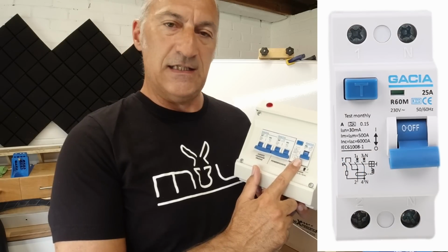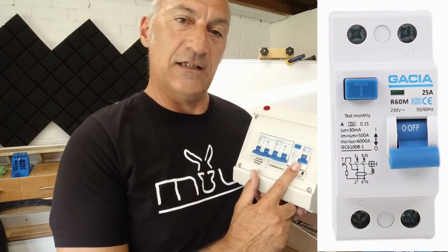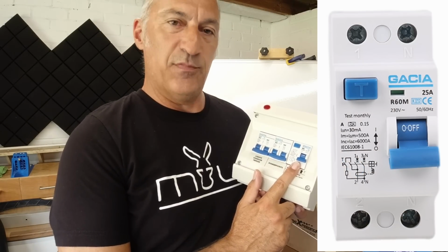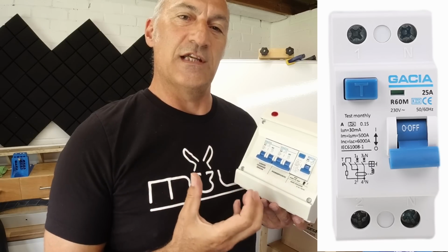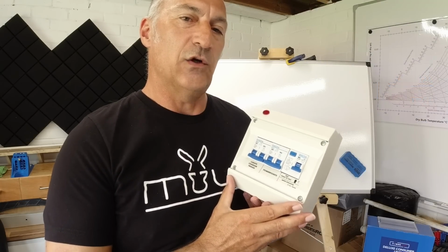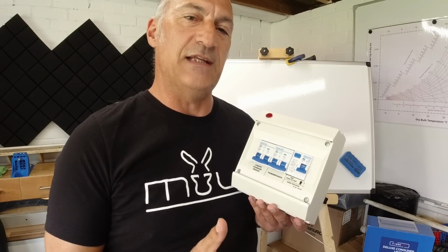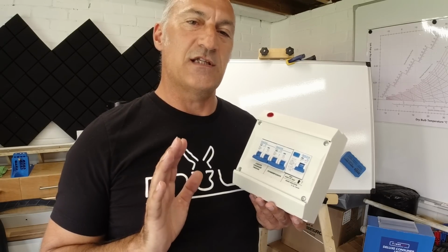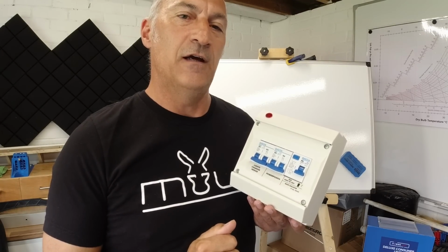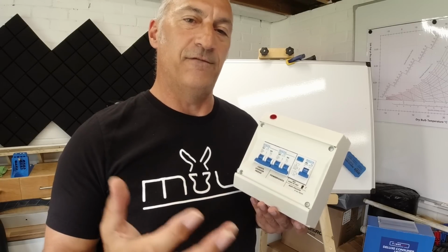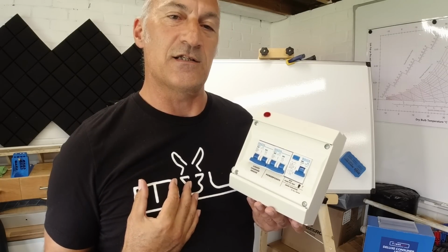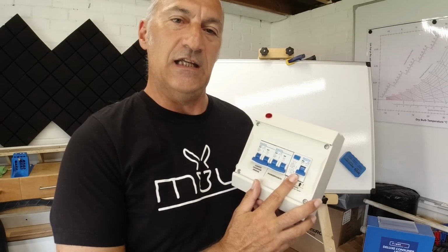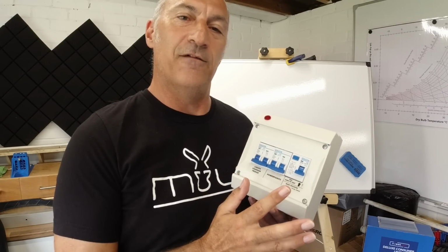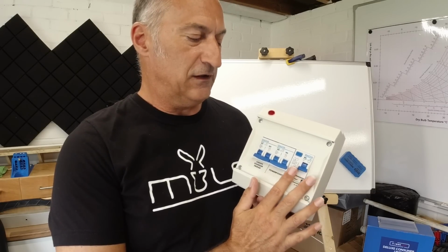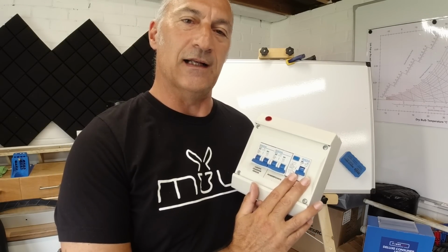There's an RCD or residual current device, and this is here to protect us from receiving a fatal shock. So if there's a fault to earth on the system downstream and we perhaps touch an appliance which is live, we're not going to receive a shock that could actually kill us. This RCD device will detect that fault to earth and it'll isolate the circuit really quickly.